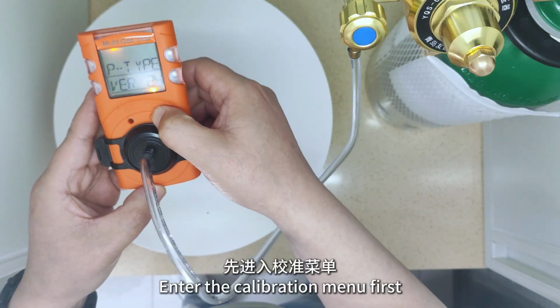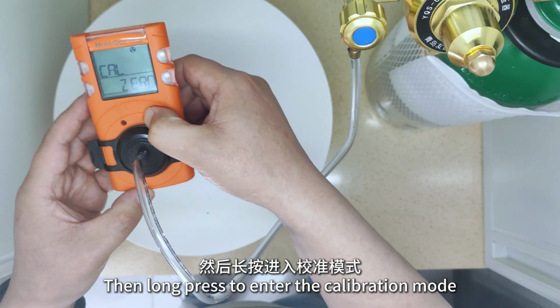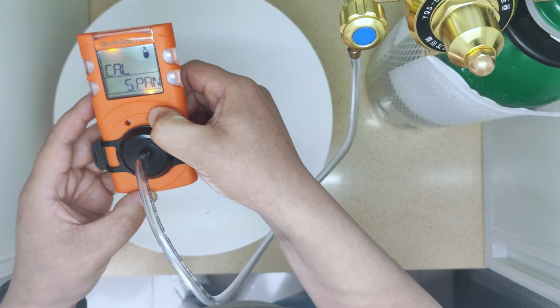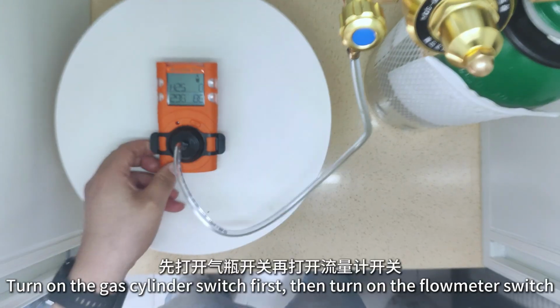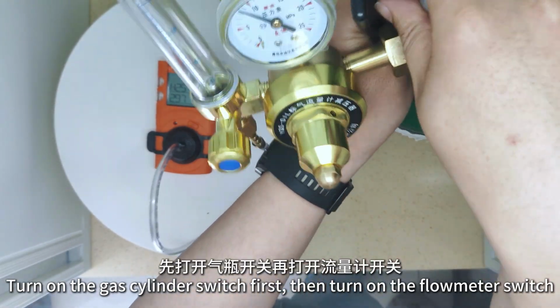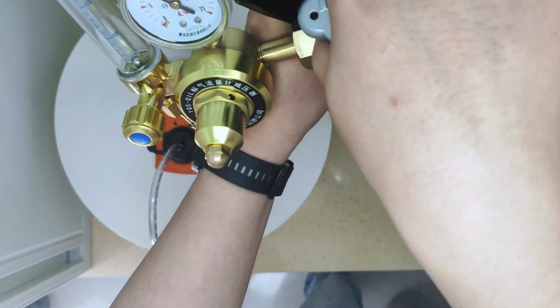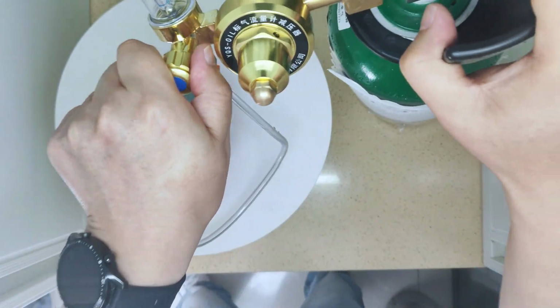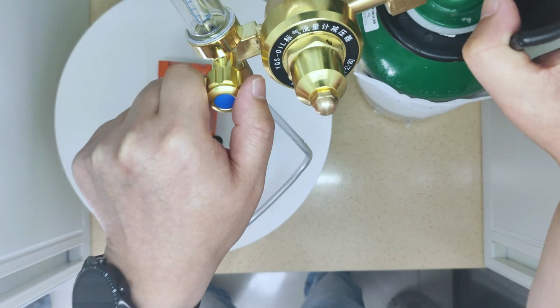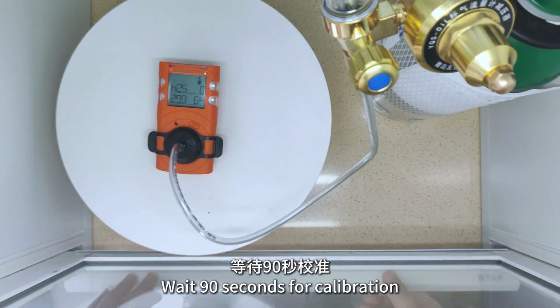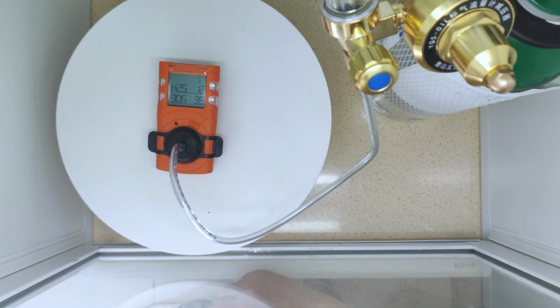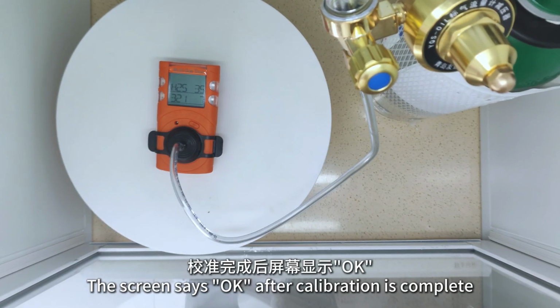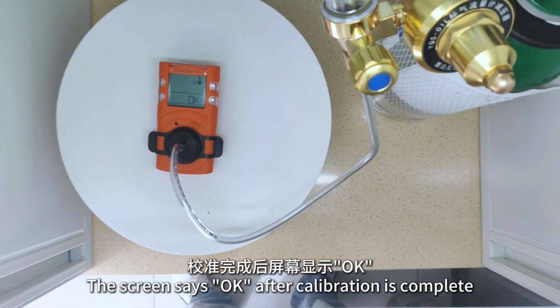Enter the calibration menu first. Then long press to enter the calibration mode. Turn on the gas cylinder switch first, then turn on the flowmeter switch. Wait 90 seconds for calibration. The screen says OK after calibration is complete.